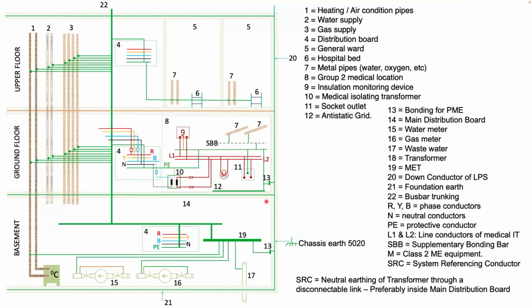The NEC in 1985 gave examples of methods of making equipotential bonding or earthing in a hospital, 1985. All these green connections, see there is a green connection, I'm sure you are able to see the cursor I am moving. This is the earthing. Finally, the entire metallic parts are bonded to serial number 19, which is the MET, main earth terminal. 1, 2, and 3 are heating pipe, water supply pipe, gas pipe, and so on. Now 7, again heating or gas pipe.